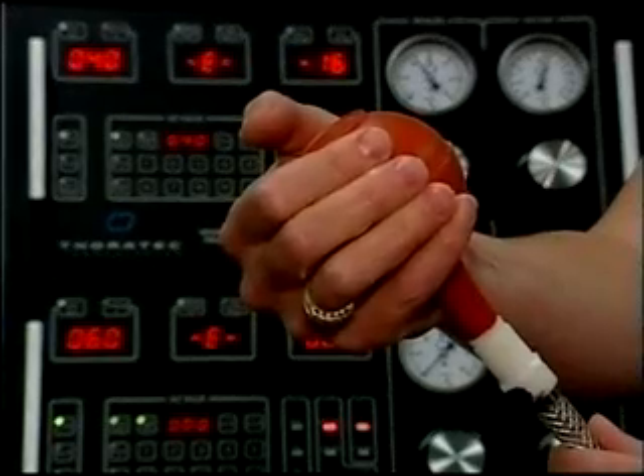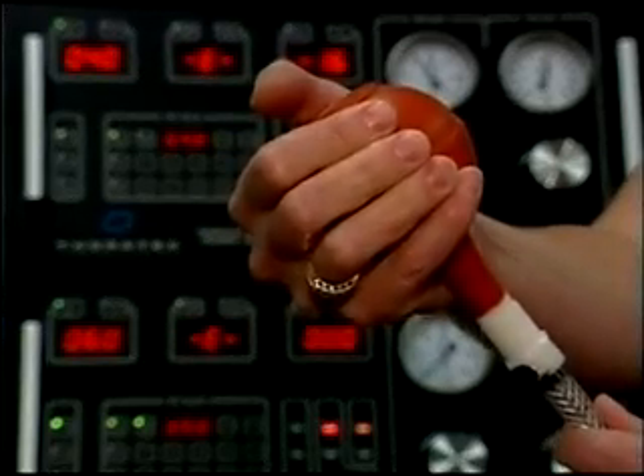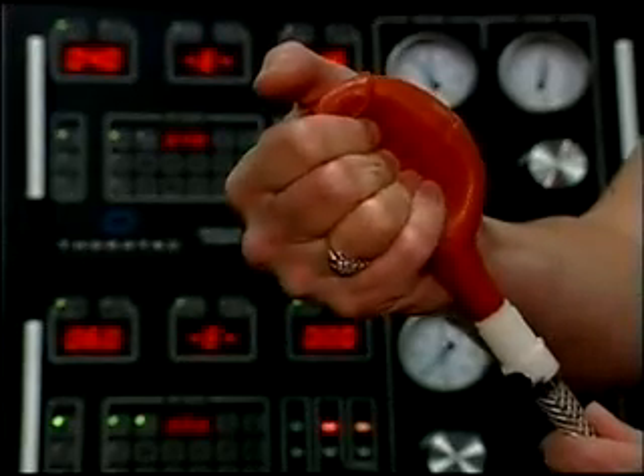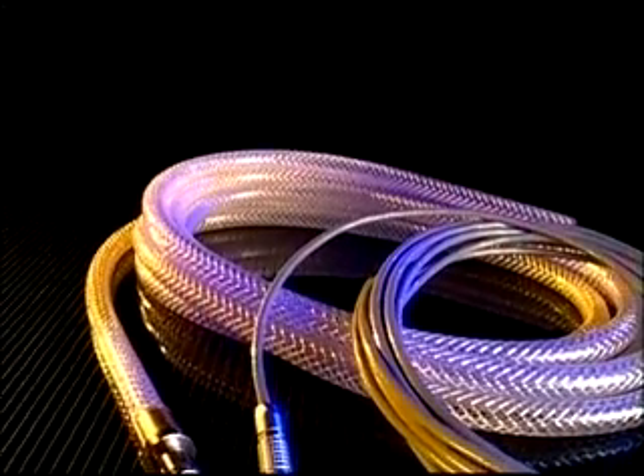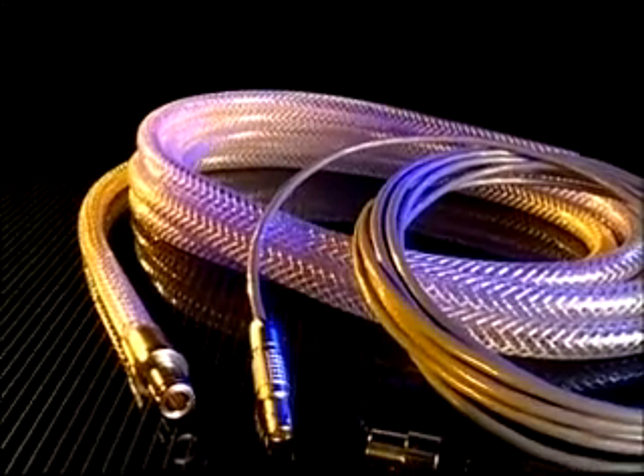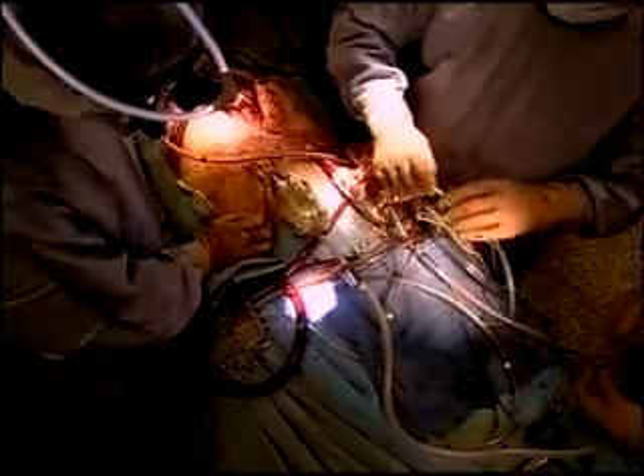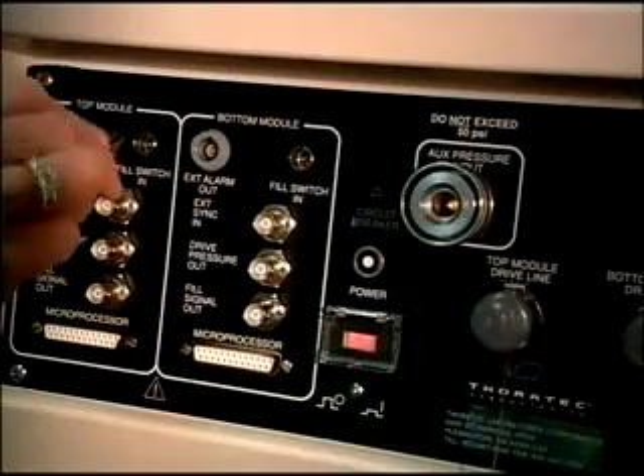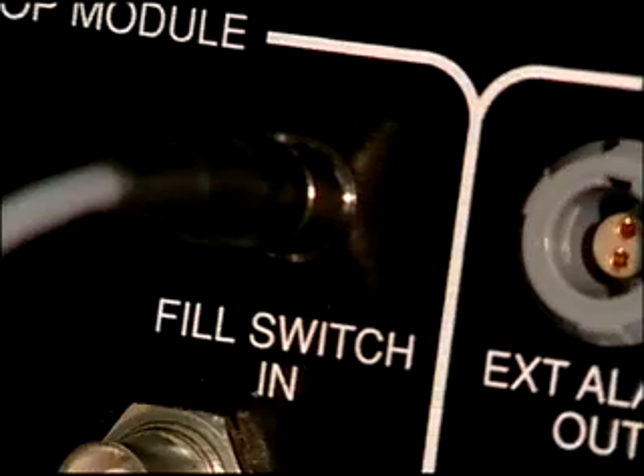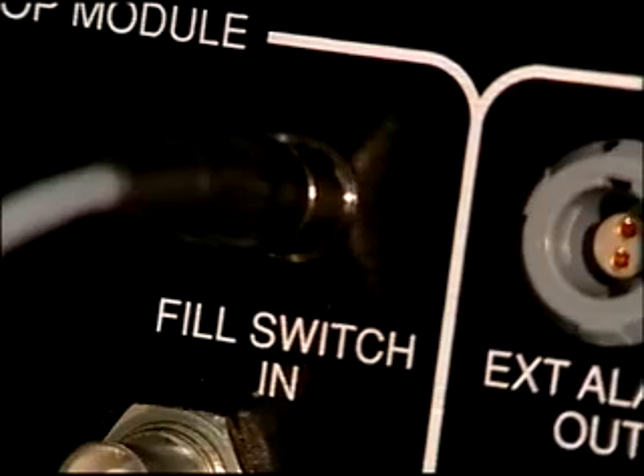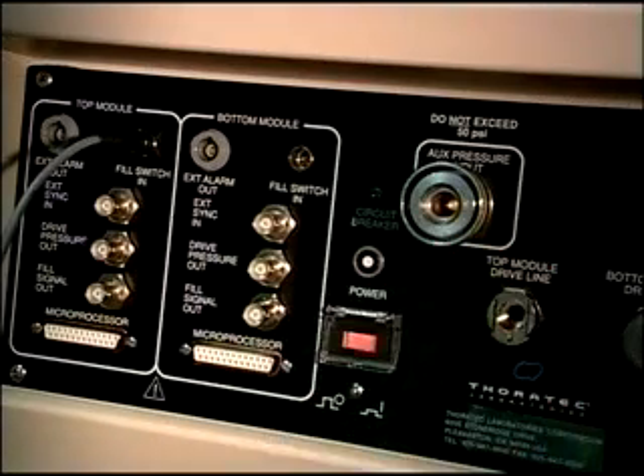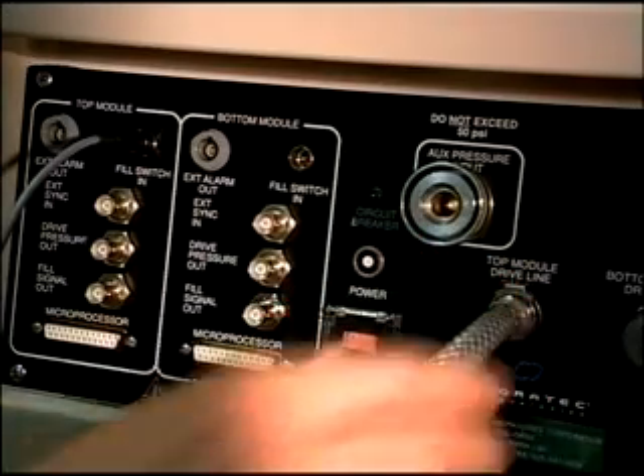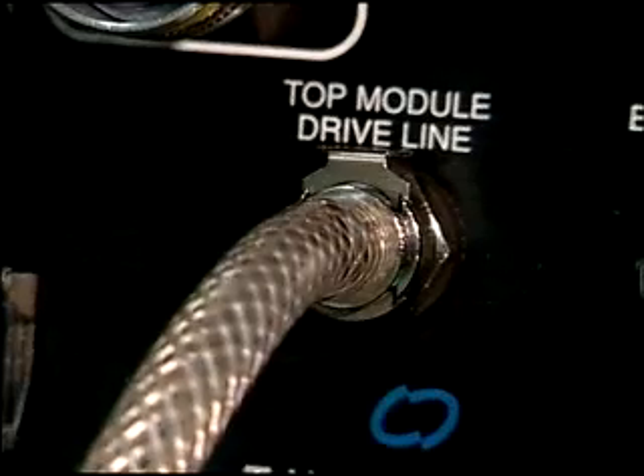During surgery, the VAD pumps are manually de-aired using hand pump bulbs. Once the VAD pumps have been properly de-aired, the next step is connecting the pneumatic and electrical leads to the appropriate drive module. The electrical leads are supplied sterile. One end will be passed from the surgical field and plugged in to the console at the appropriate fill switch in port. The pneumatic leads are also supplied sterile. Each should be inserted into its corresponding driveline port.